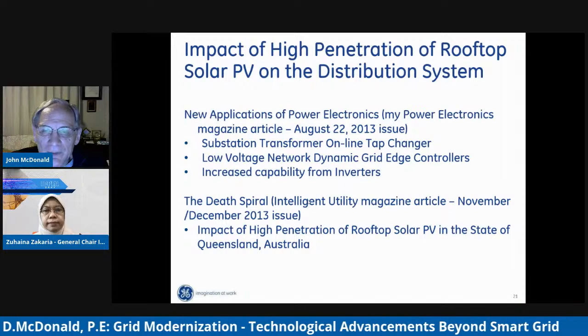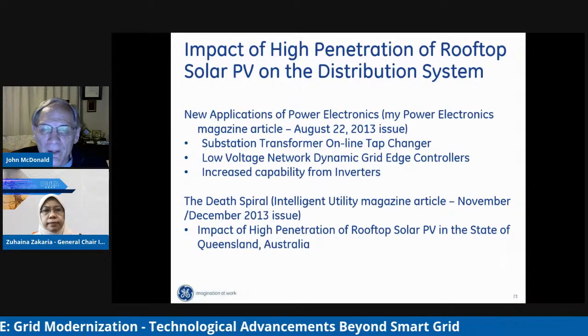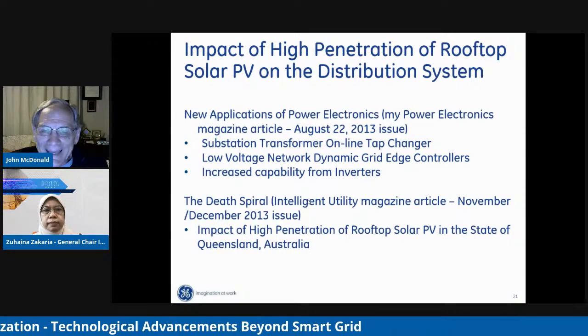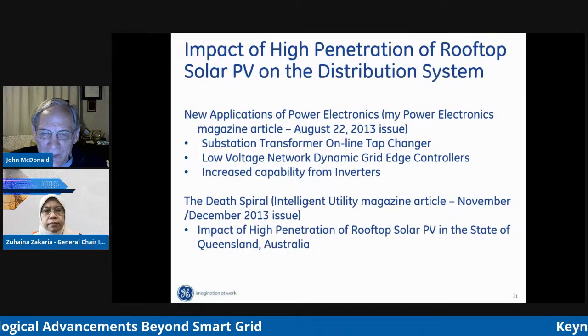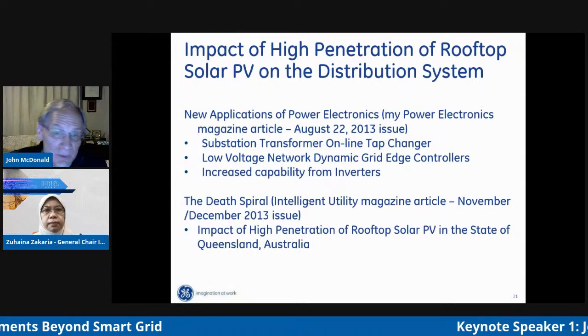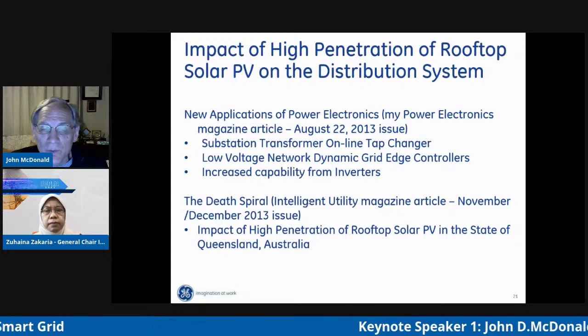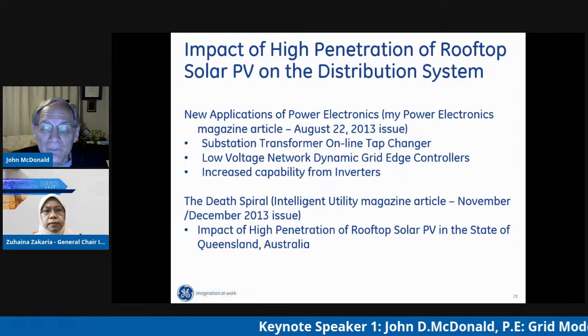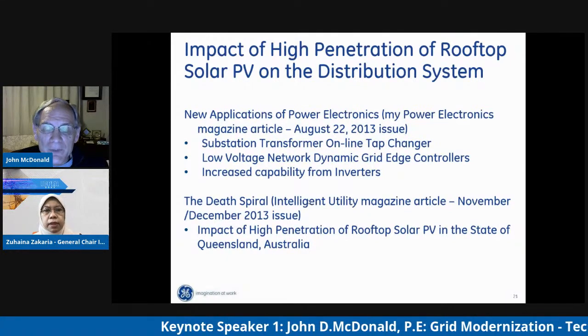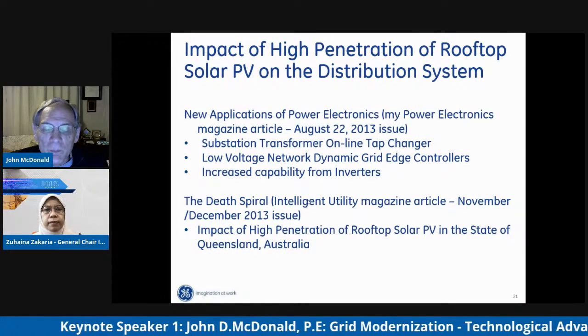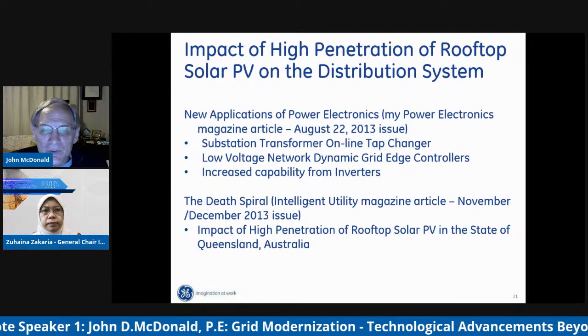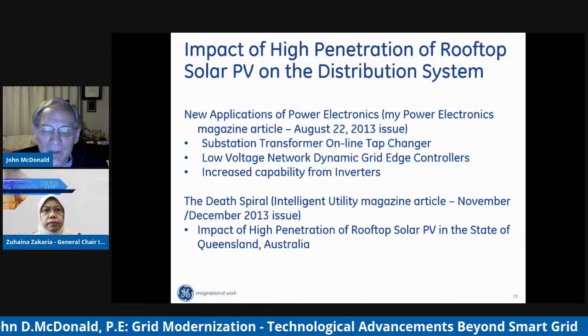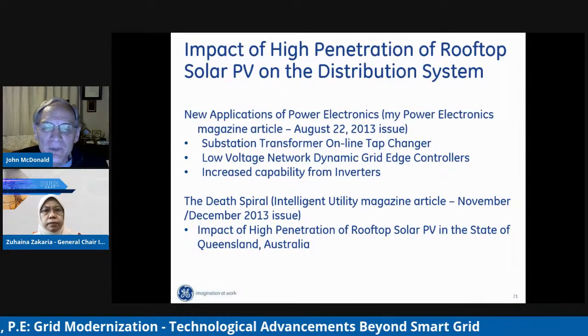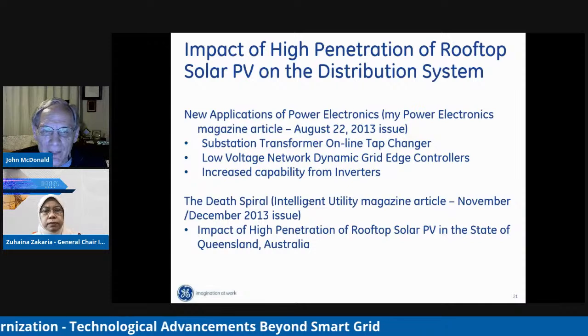What happened, do you think, to the tap changer in the substation? A tap changer is a mechanical control device—16 raise positions, 16 lower positions, and 1 neutral position—but it's mechanical. It operates more frequently when the primary voltage changes more often, because its goal is to keep the secondary voltage constant.